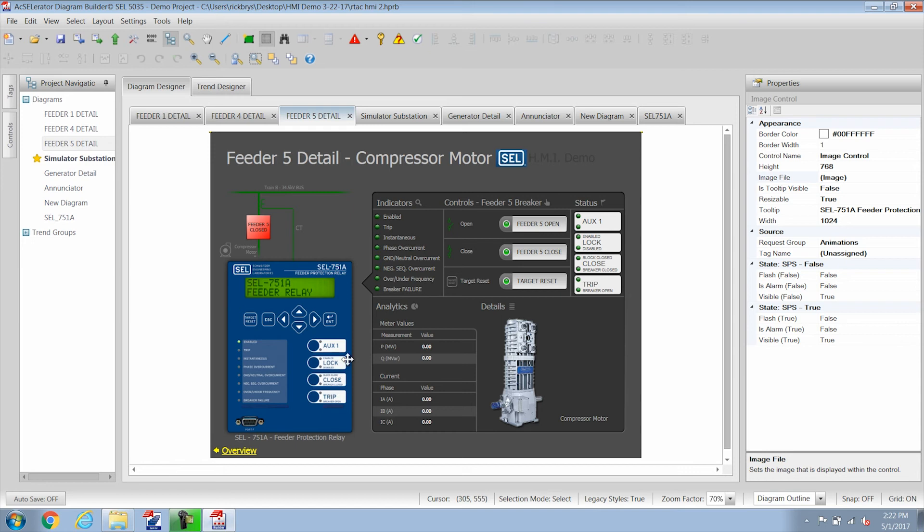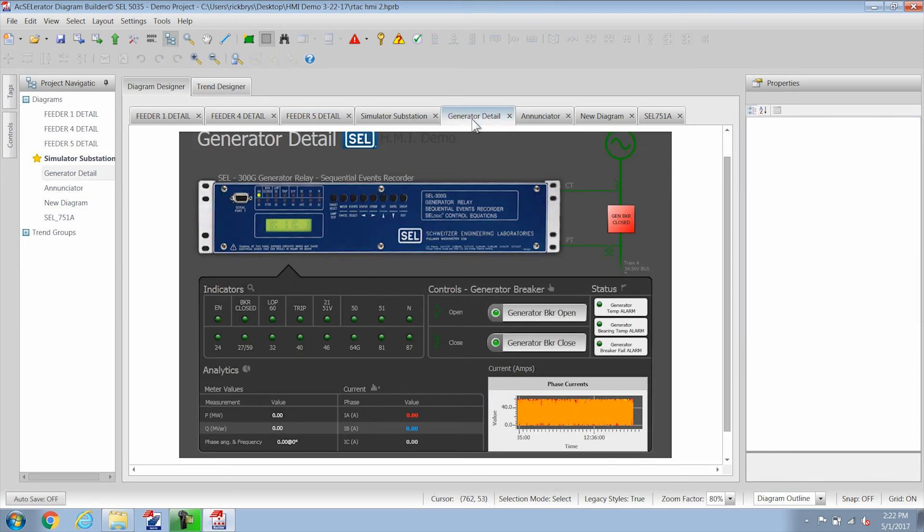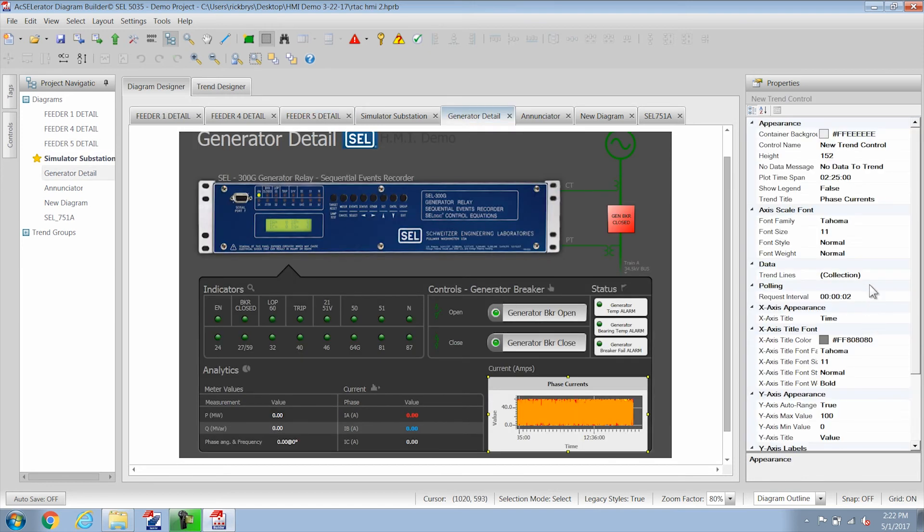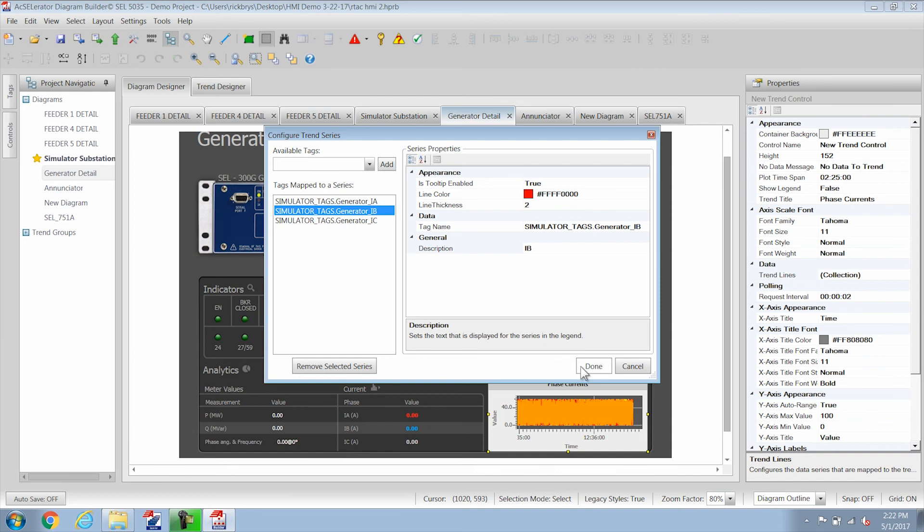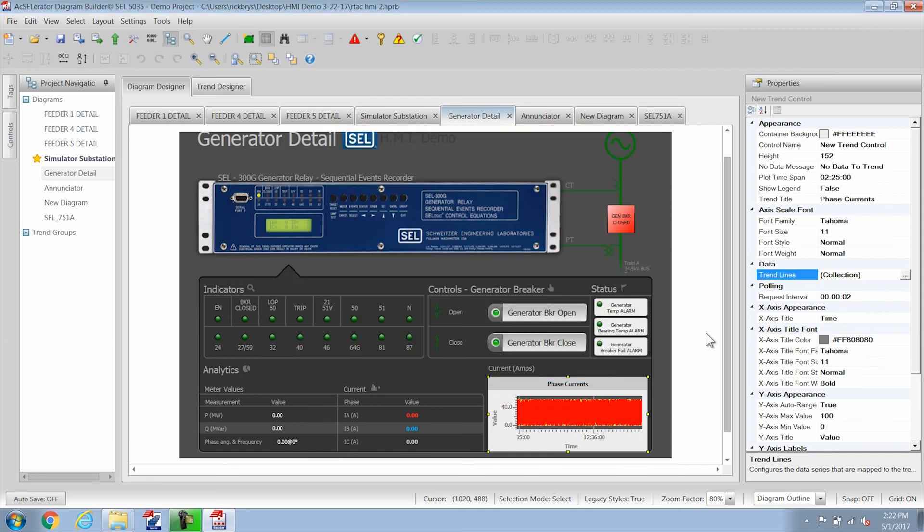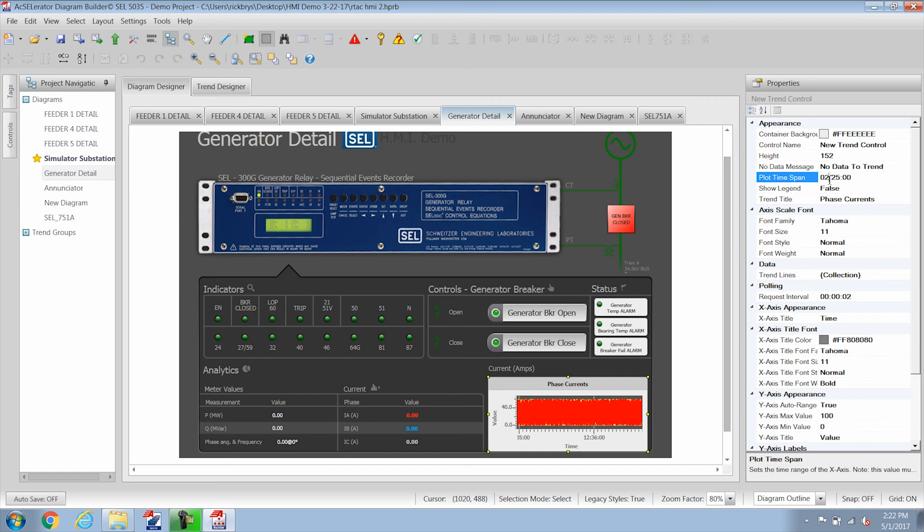You can also embed trends. So we did that in this image here and when you select the tags for the trends then you can change the attributes of the tags to be red or whatever color you want for the line and also change the min and max size of the X and Y coordinates. And the plot time goes up to 24 hours and the plotting occurs while you're watching it like in Chrome or whatever. So it doesn't actually store historical values in the RTAC. It actually is just plotting real-time values.